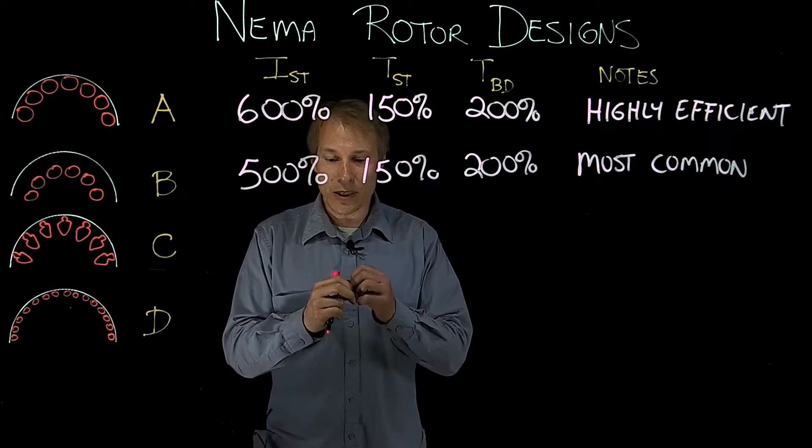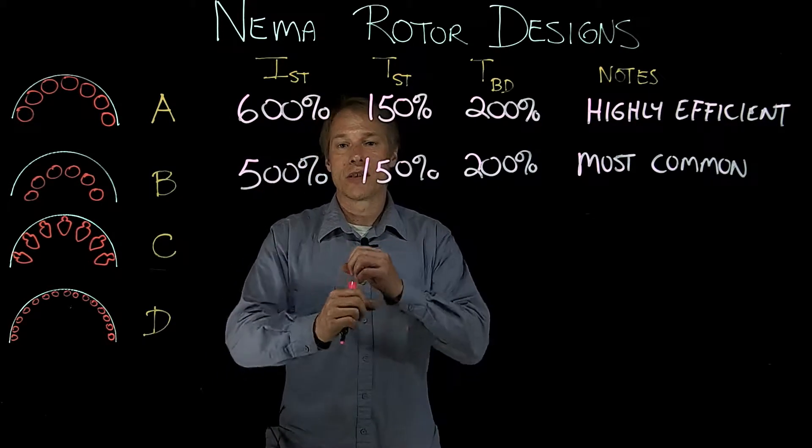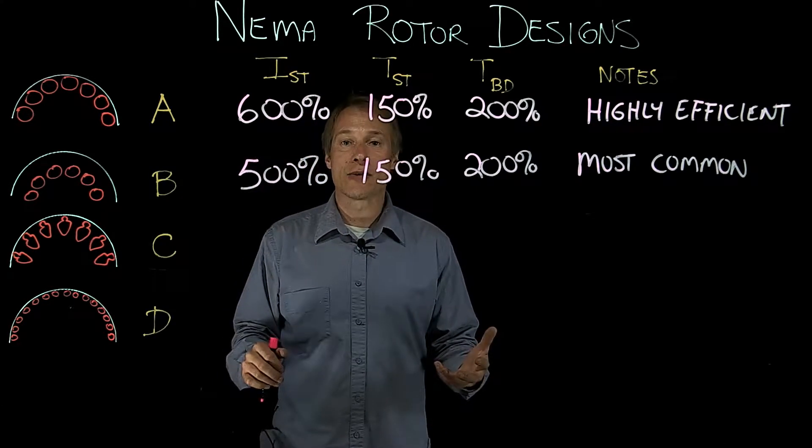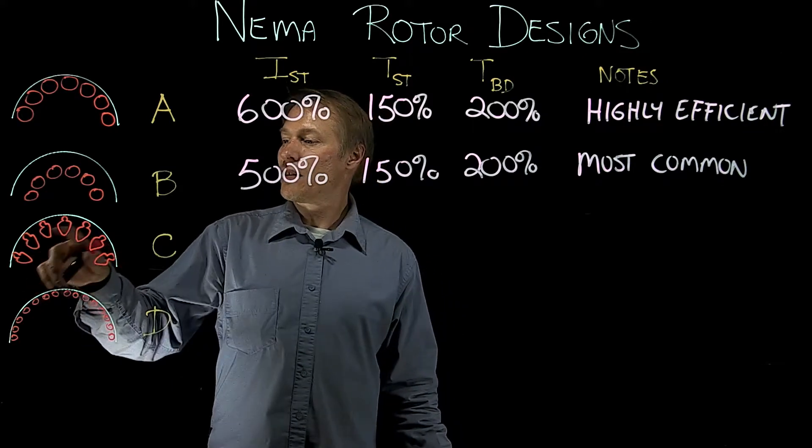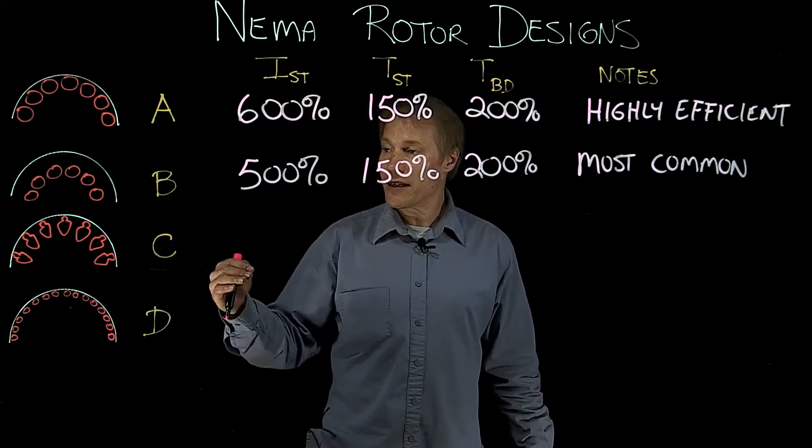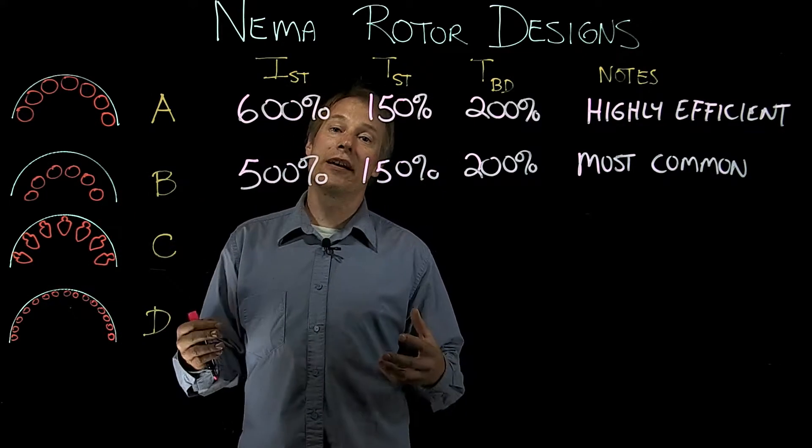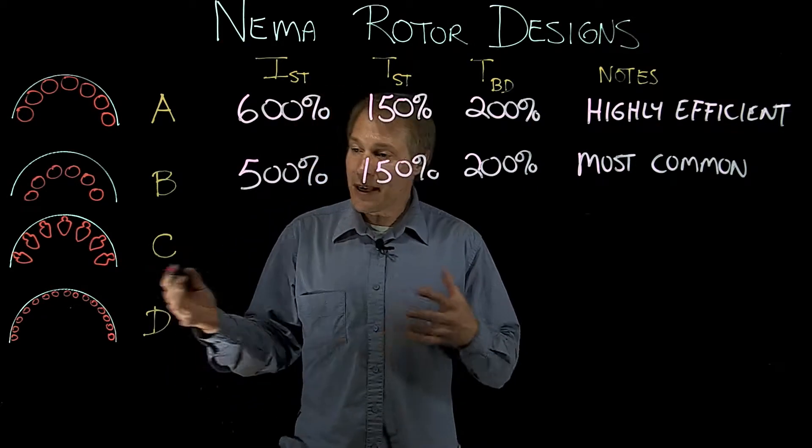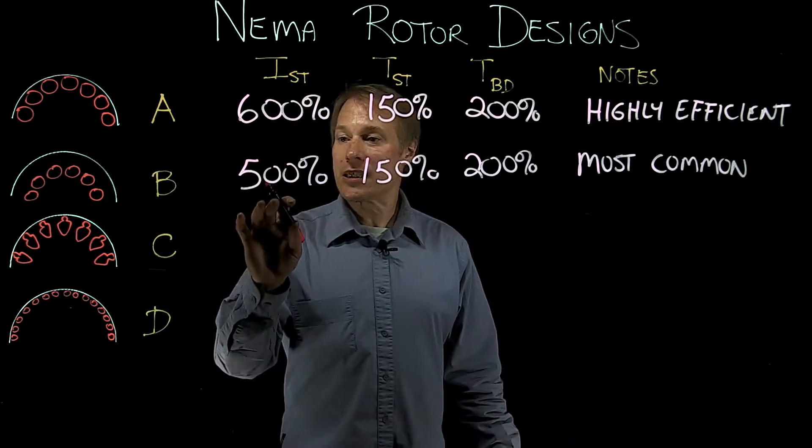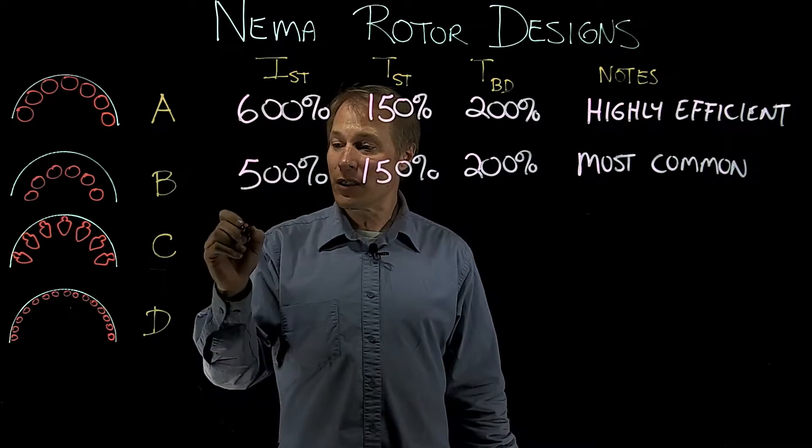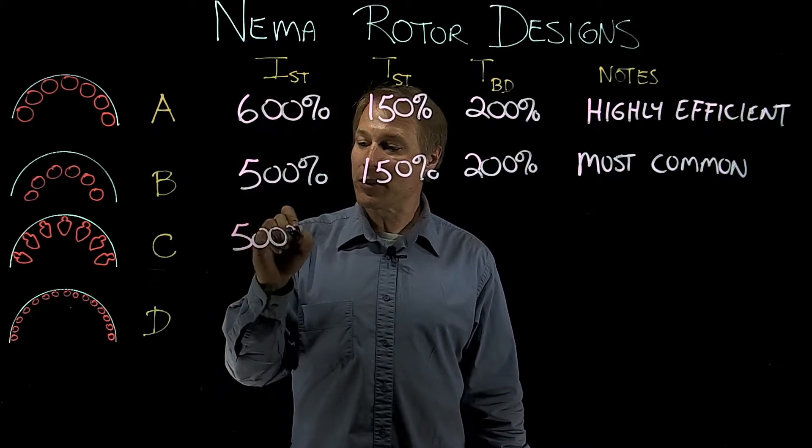Now as you can see the outer ones here are quite small, so smaller cross-sectional area gives a higher resistance. And then we have the larger ones that are embedded a bit into the rotor, so they have higher inductance. That basically evens out, so the starting current is still going to be around 500%.